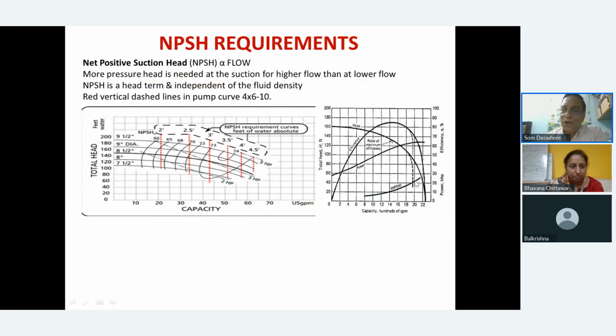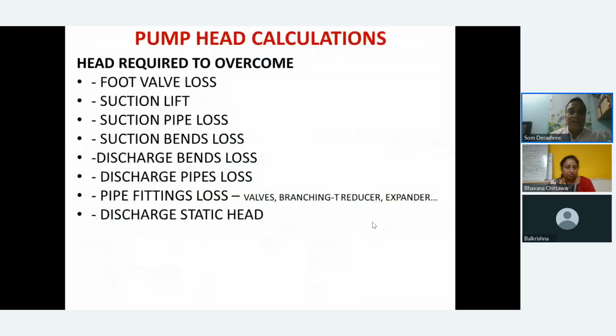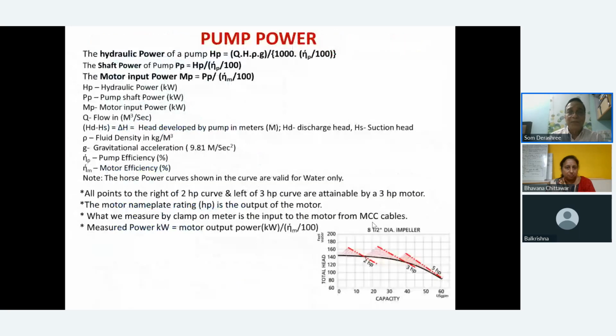So when you're talking of VFD, you will be coming into the back zone. You'll reduce, so NPSH required also will reduce, because everywhere flow will reduce. Once flow reduces, velocity reduces, your Reynolds number reduces, friction loss reduces. So everywhere there'll be reduction. So if you have no cavitation at 50 hertz, by putting a VFD, be rest assured there'll be no cavitation. But you have a problem of head, because many times people fail to understand this: if your static head requirement is very high, as I told you, a VFD you cannot put everywhere. I think I showed you one curve.